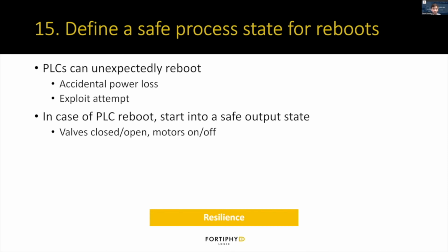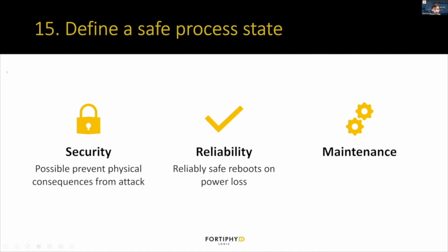And when you do detect that, you want to be able to start the PLC back into some safe state. You don't want it to just pick up. You may or may not want it to pick back up where it left off. You may want to reset it back to a safe state, so it doesn't cause any unexpected problems picking up in some kind of random state where it left off. For security, this helps possibly prevent physical consequences from an attack. If they brute force it to cause a reboot and you start back up into a safe state, then you've hopefully avoided any physical damage. Maybe you just caused some downtime, but you avoided physical damage from it starting up in a state that causes problems. For reliability, this helps ensure you get safe reboots if you do accidentally lose power.